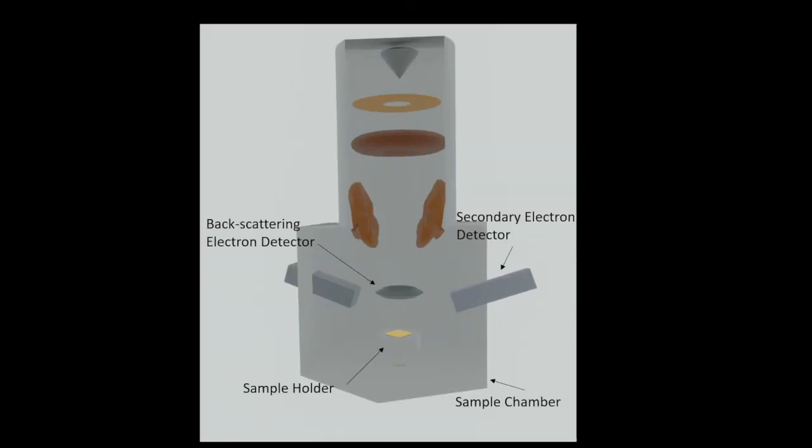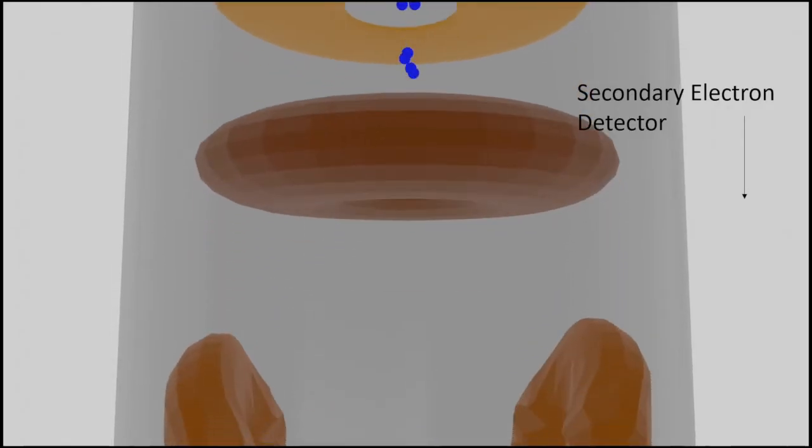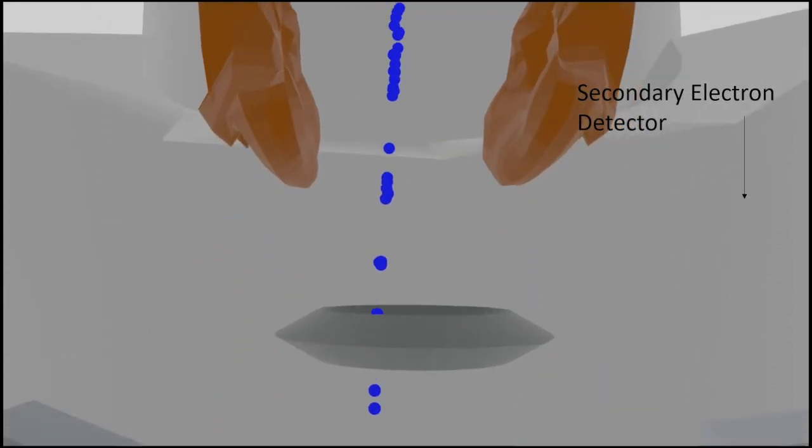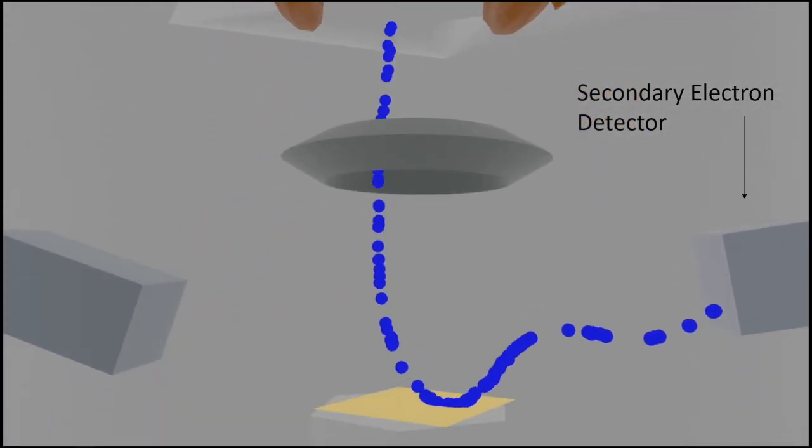Moving on to the bottom half of the SEM, the SEM has a sample chamber and a sample holder. The sample holder is where the sample is placed to be analyzed. Now the sample chamber is where the detectors are held, such as the secondary electron detector and the backscattering electron detector. The secondary electron detector is for the secondary electrons that come out of the sample when being hit by an electron beam. Those electrons are then picked up by the detector giving unique signals that are analyzed by the computer to give a surface image.